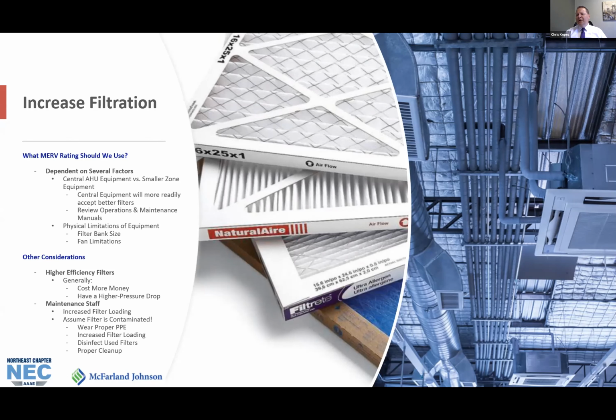So other things you want to consider for your maintenance staff, with COVID-19 having the potential to be airborne, these airborne particles are eventually going to find themselves in your HVAC system and hopefully caught by your equipment's filter section. So a couple things. You might be thinking you should increase the frequency of the filter changes. Actually, ASHRAE recommends quite the opposite, reducing the frequency of the filter changes if possible. So this is going to reduce the exposure of maintenance personnel to the potential contaminants, as well as reduce the risk of these particles being reintroduced back into the building.